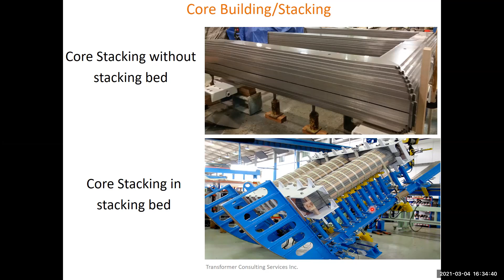So now over here, this picture I have taken from a factory. I went to the factory for core and coil inspection. Overnight it rained. Next morning when I went to the factory, the factory not being climate controlled and the humidity being high, the core got rusted. Now the rust is a killer for the transformer performance. Why? This rust is not magnetically conductive, so it's going to compromise the magnetic property of the core. That means it's going to compromise the quality of the transformer.